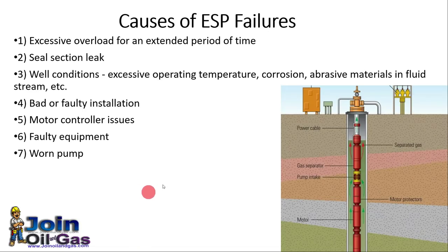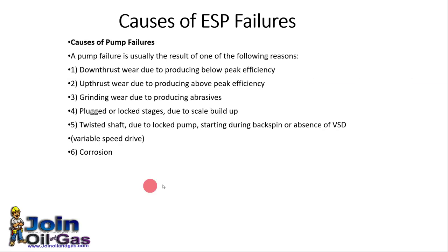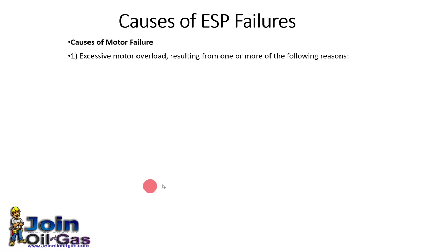Causes of ESP system failure include excessive overload for extended periods, seal section leaks, unfavorable well conditions, poor or faulty installation, motor controller issues, faulty equipment, or a worn pump. Causes of pump failure include down-thrust or up-thrust, plugged or locked pump, or corrosion problems. Causes of ESP motor failure include excessive motor overload and abnormally high specific gravity, which may cause the motor to fail.